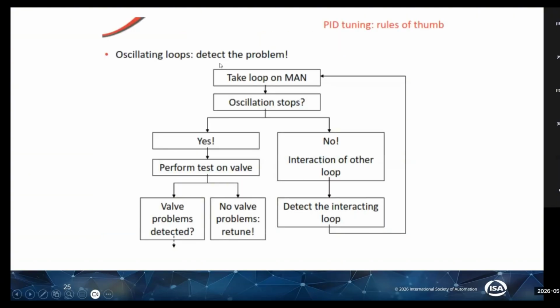So here I can show you that before tuning a controller, you have to detect the problem. What you can do is take the loop in manual. You have been informed that the controller is performing badly, so first ask the operator if he can take it to manual. If it is not very critical, he will take it. If oscillations stop, perform a test on the valve. If a valve problem is detected, then you have to fix it. Otherwise, it's a tuning issue. So if oscillation stops in manual, that means it's a controller issue.